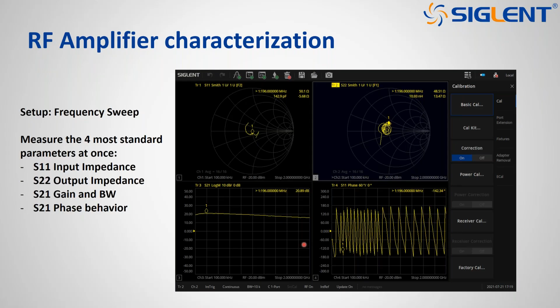For RF amplifier characterization, as I mentioned before, we measure input impedance, output impedance, the reflections, and also the transmission, for example. These are the main ones which you can do at once. Modern VNAs can also have many more windows. Our SIGLENT one can have up to, I don't know, 64 windows, which is very huge, and you don't see anything in real. But 16 or 8 windows are quite common, and you can have everything connected and calibrated once. You set up everything once, then you can measure everything step by step, get all the data out of your system, and get it into your simulation or your design software.